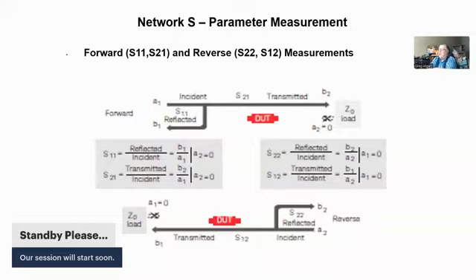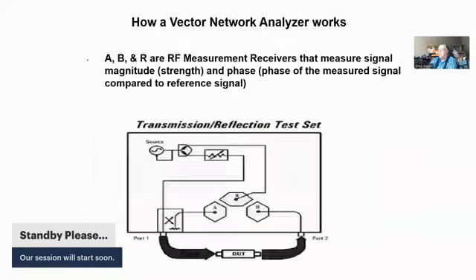And the way to kind of remember it is the S stands for scattering. The first number is the signal is applied to the first number, and then you look at the signal coming back or coming out of the second number. So if we would take, for example, S21, it would be the signal at port 2 when a signal is applied to port 1. And S11 would be the signal at port 1 when a signal is applied to port 1. So that would be the reflected signal from port 1.